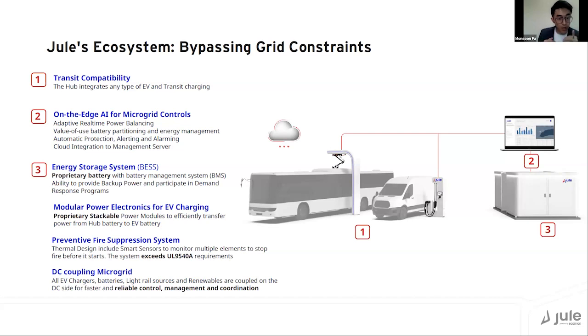In addition, we have a preventative fire suppression system inside the cabinet that exceeds the requirements for UL 9540A. A lot of batteries today only respond to fire after an accident. We actually put AI into it to predict when an accident may happen, so the fire suppression can act at a very early stage to mitigate the possibility of thermal runaway, because in battery technology, once thermal runaway happens, there's very little we can do but keep splashing water to cool it down.